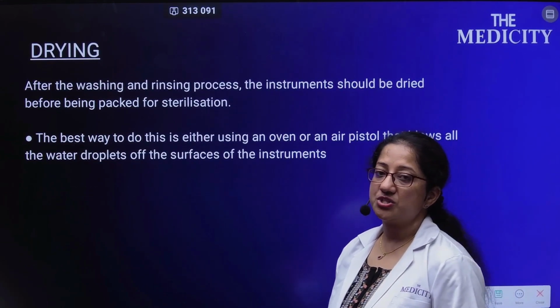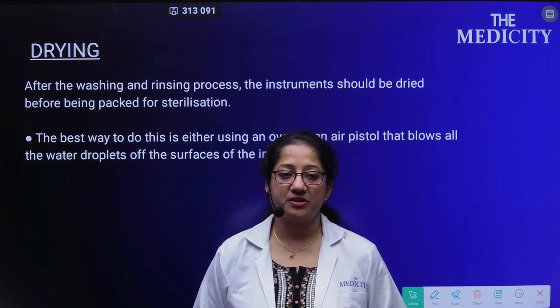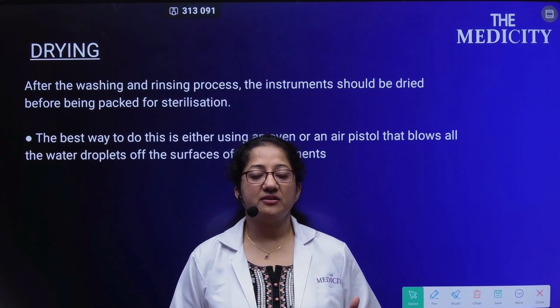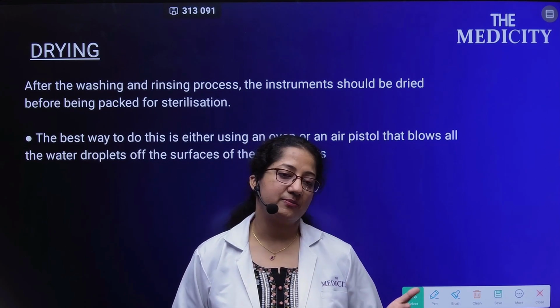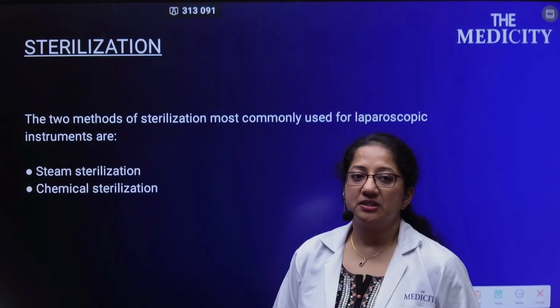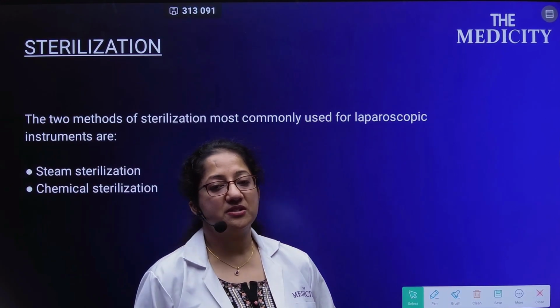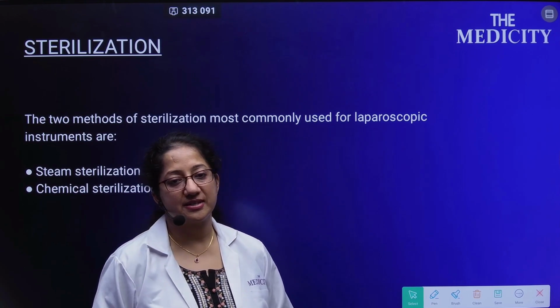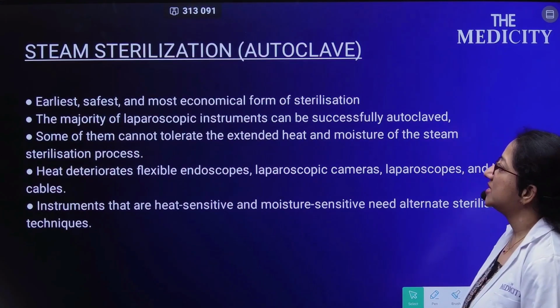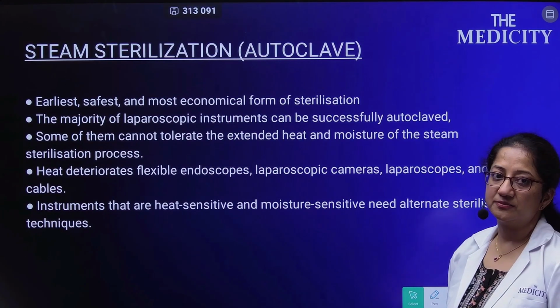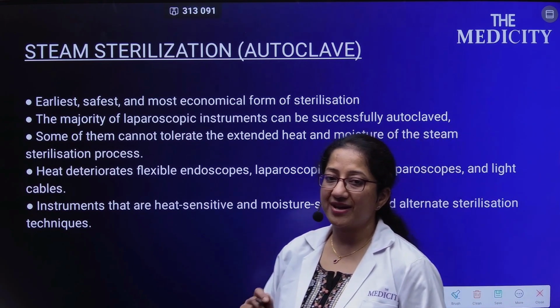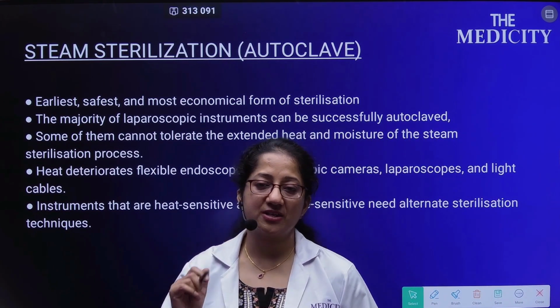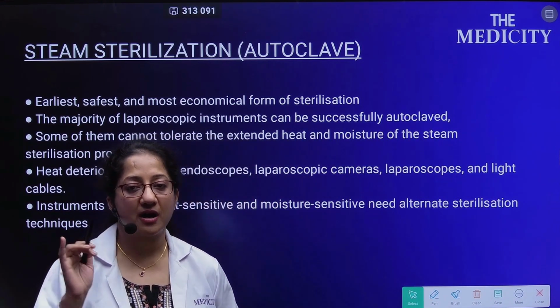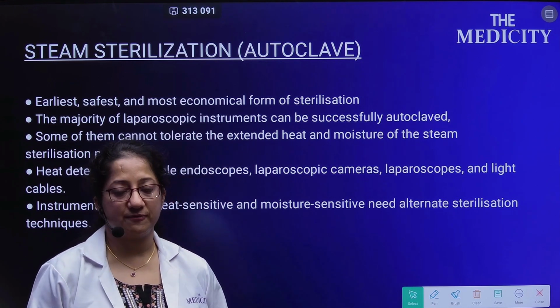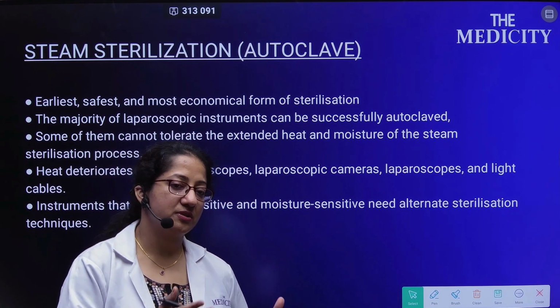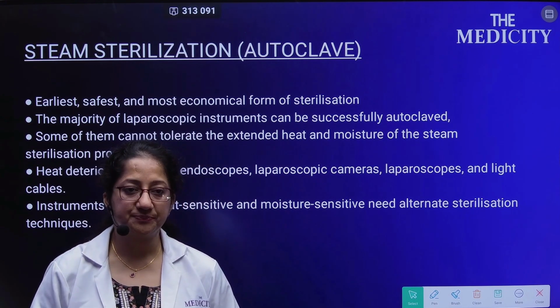Drying. After the washing and rinsing process, instruments have to be dried. The best way is either in an oven or with an air pistol that blows all the water droplets away. Now sterilization. We have two methods, steam sterilization and chemical sterilization. Steam sterilization, that is the autoclave. This cannot be used for every laparoscopic instrument. It can actually harm; maybe the harmonic scalpel cannot be put in an autoclave. That basically has to be put in a specific steam sterilizer.